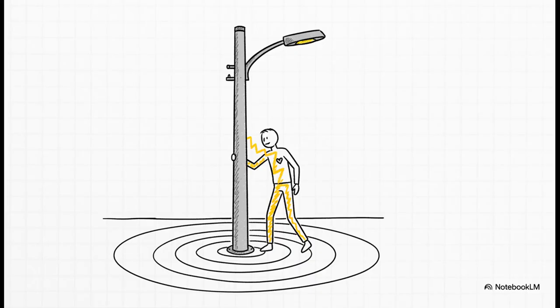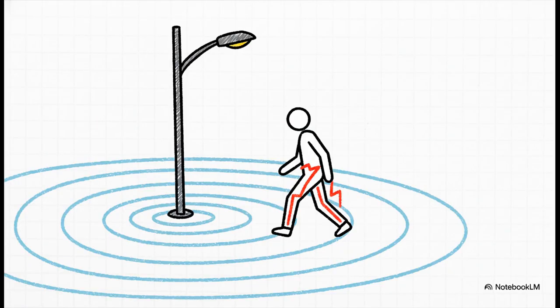Scene 2: somebody walks up and casually leans against the pole. Their hands are now electrified, but their feet are on the ground a little ways away, which is at a much lower voltage. We've just created a perfect path for electricity, and that person is experiencing a potentially fatal touch potential shock. Meanwhile, another person is just walking past, minding their own business. As they take a step, one foot lands on one of those voltage ripples, and the other foot lands on another, creating a voltage difference right across their body. They're getting a step potential shock without ever even touching the streetlight.